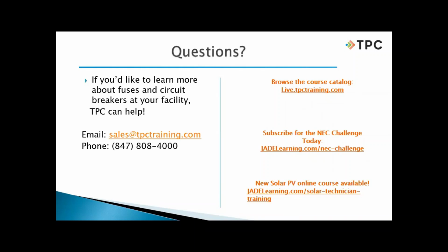But we have so much more than just that term, because we have to bring that connection to our equipment. We do that with an equipment grounding conductor, which is green or green with one or more yellow stripes. Then we also ground our neutral conductor at our service, and we call that a grounded conductor. We have two-day seminars on grounding and bonding that are very technical, but basically earthing and grounding is a connection to earth through a grounding electrode.